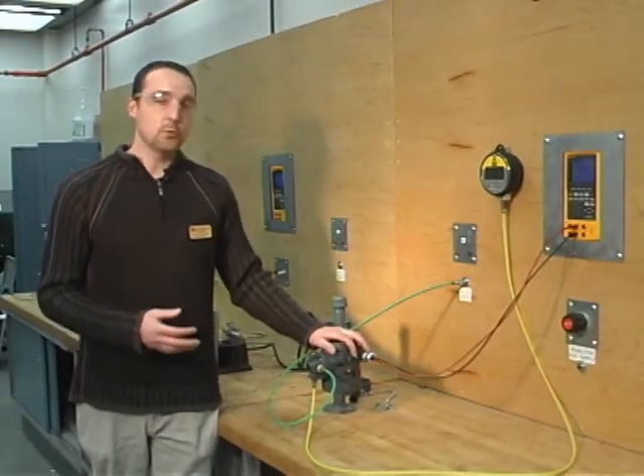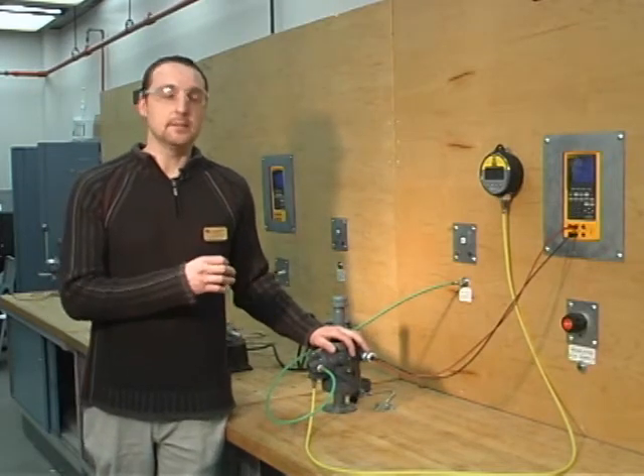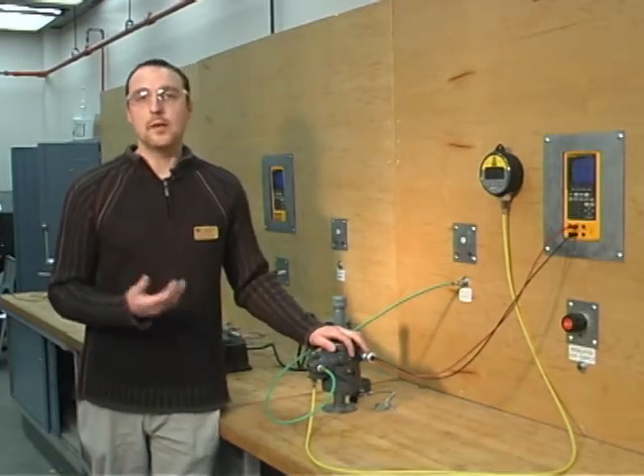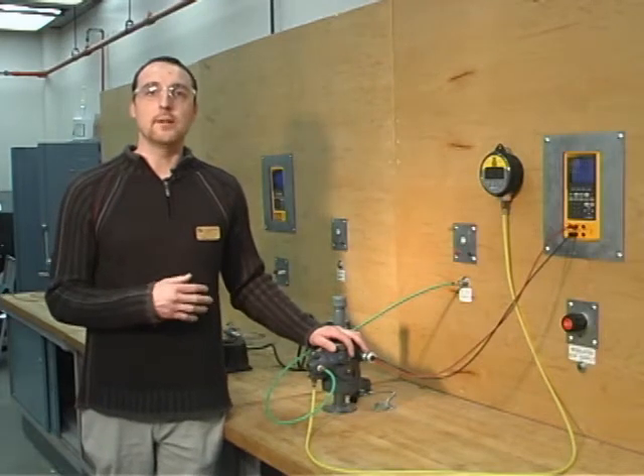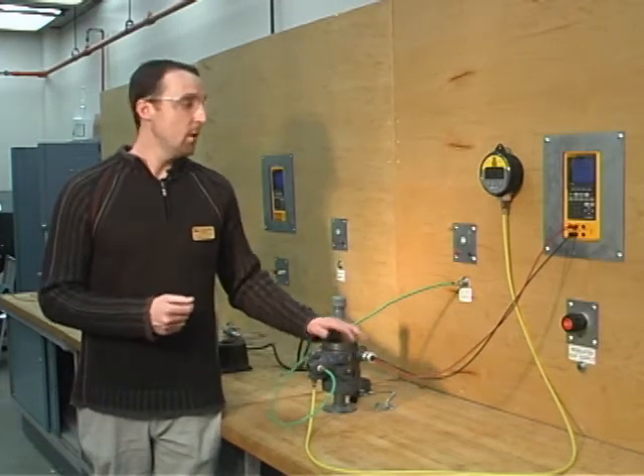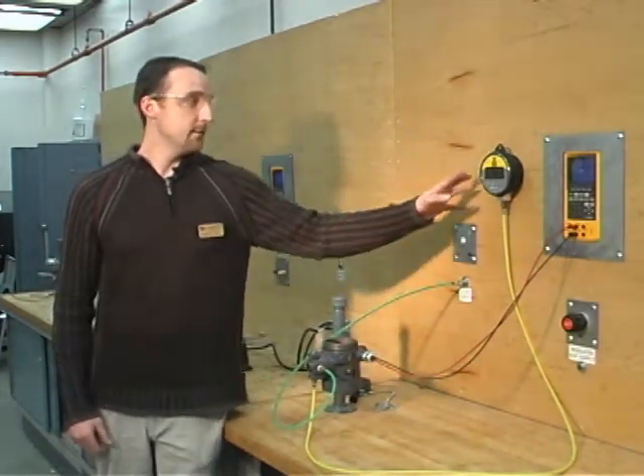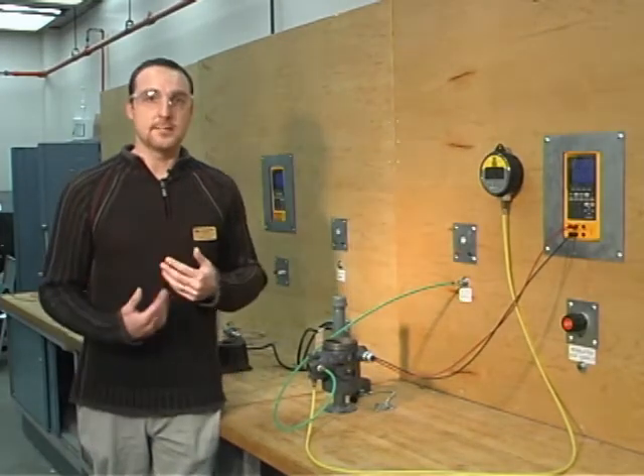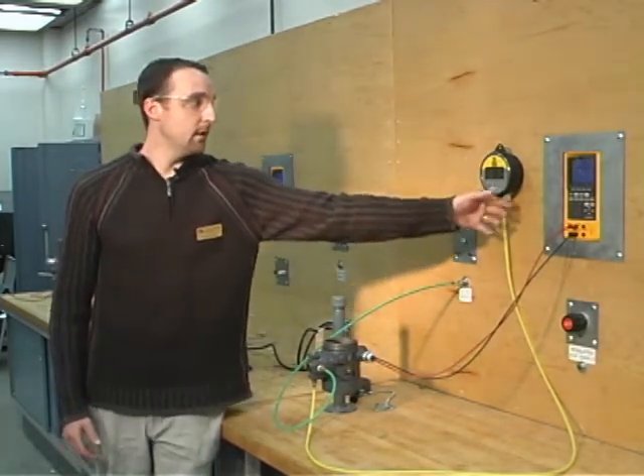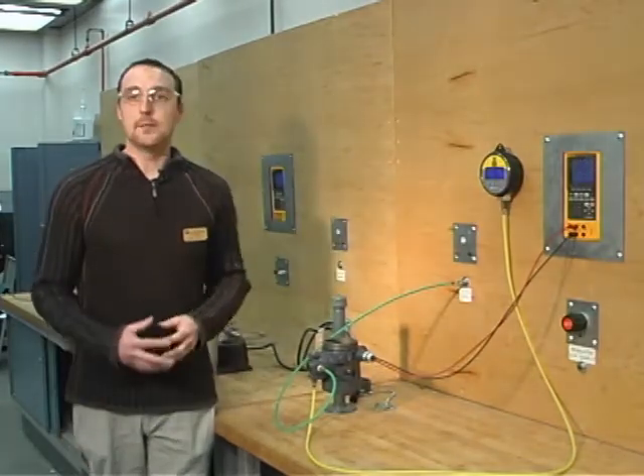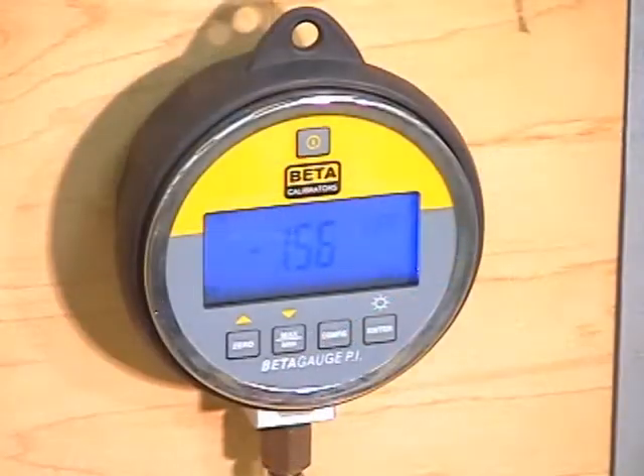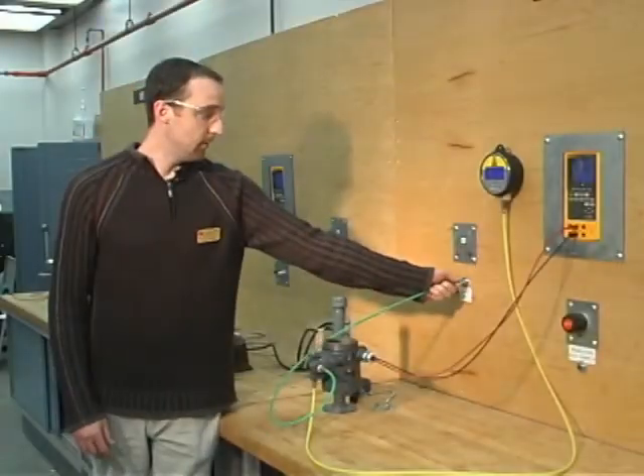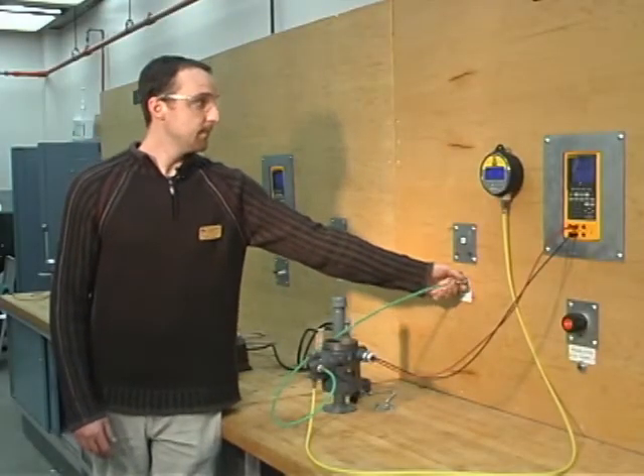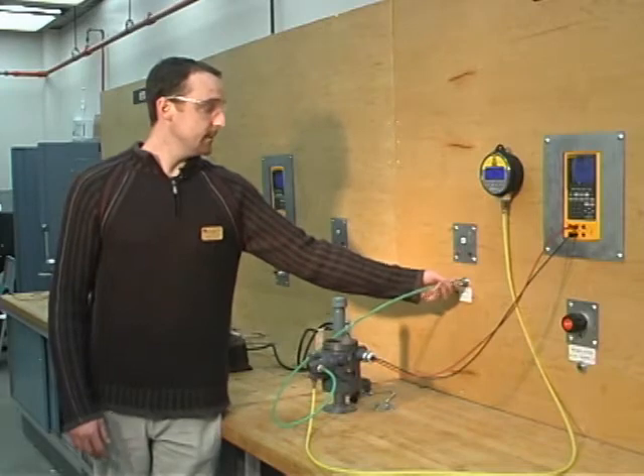An ideal place where a transducer or an I/P such as this would be used would be on or near a valve to open at 3 to 15 psi or 20 to 100 kilopascals. For our experiment today, we're going to be reading our measurement in kilopascals. Now that we are wired up, I'm going to connect our pressure to our transmitter.